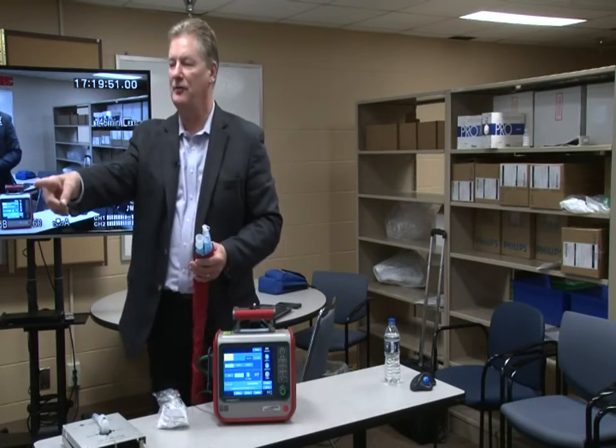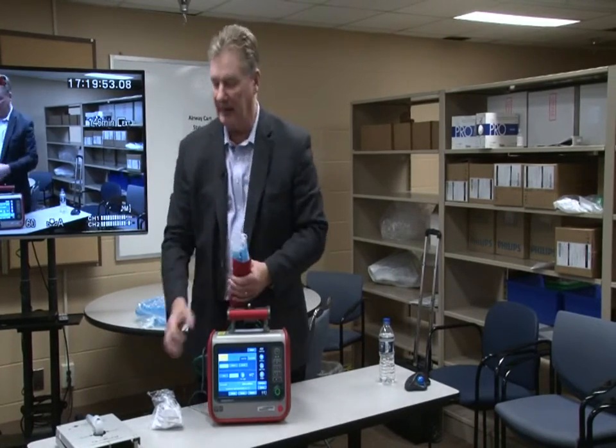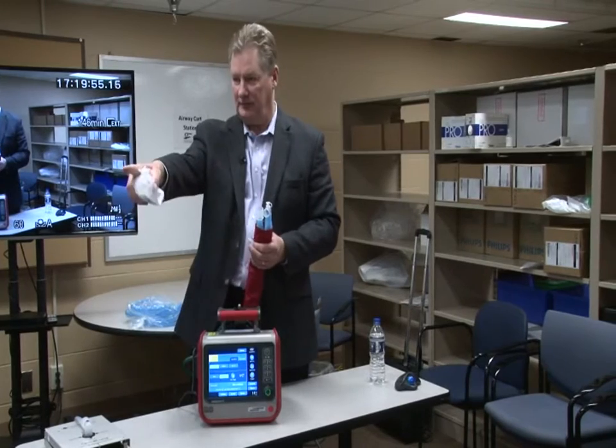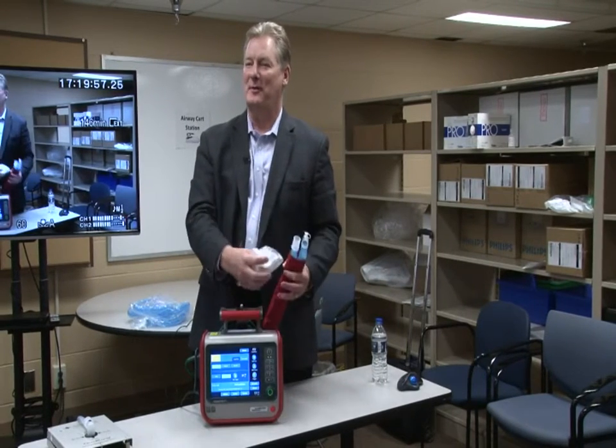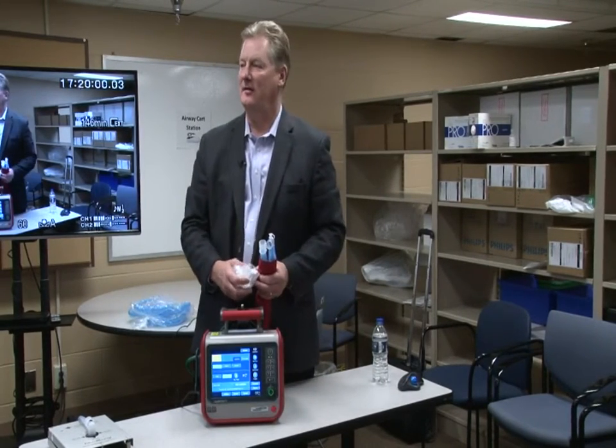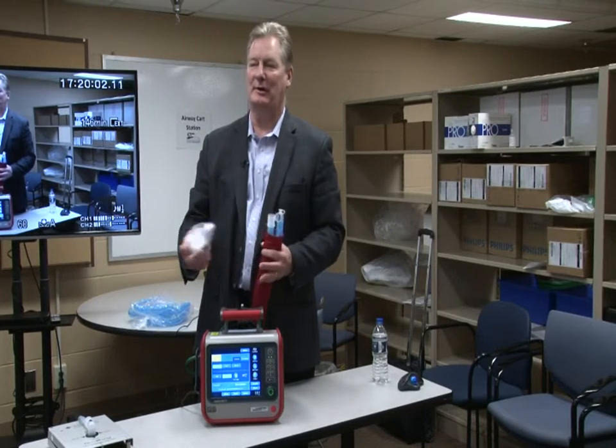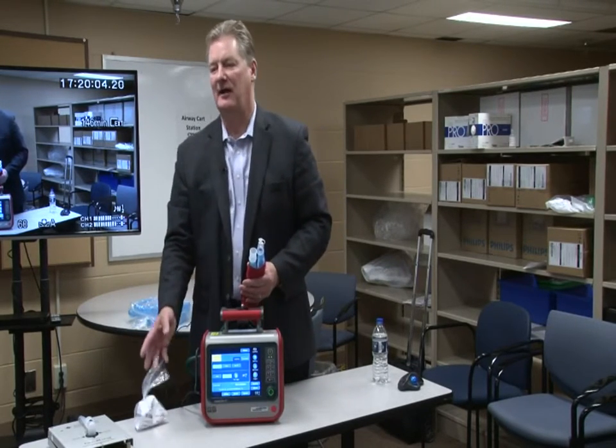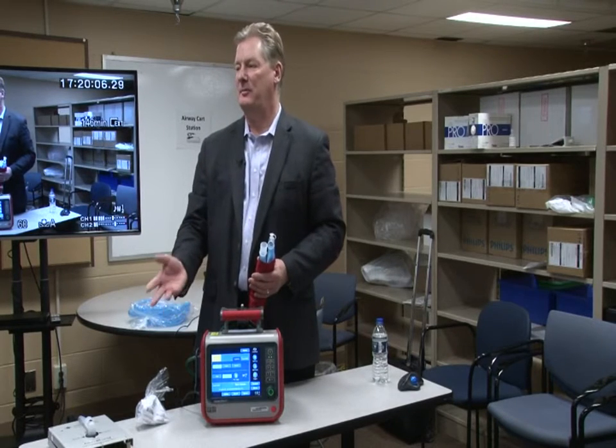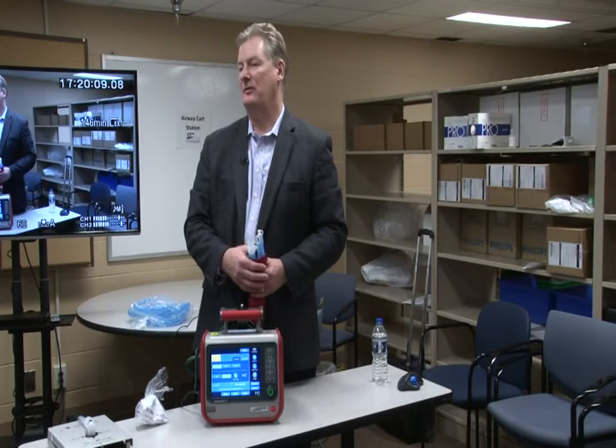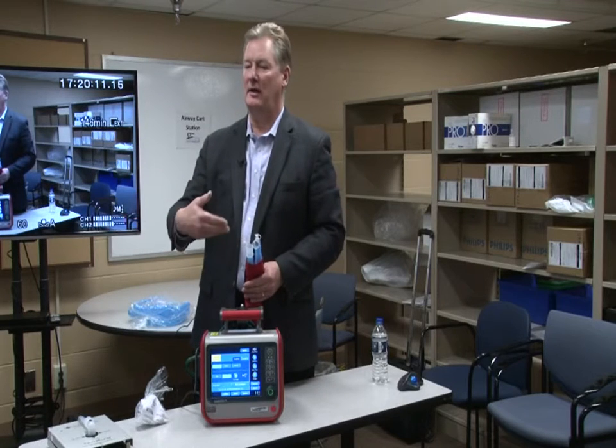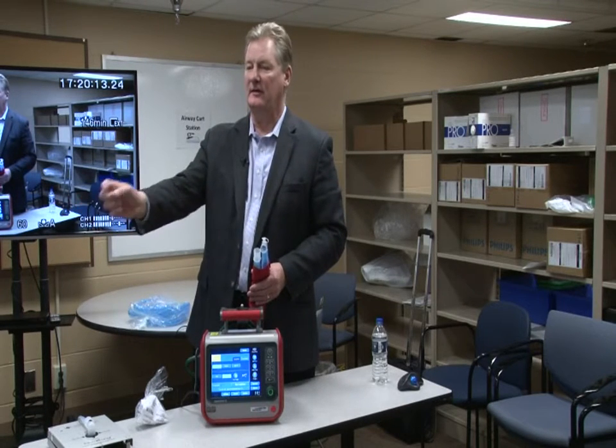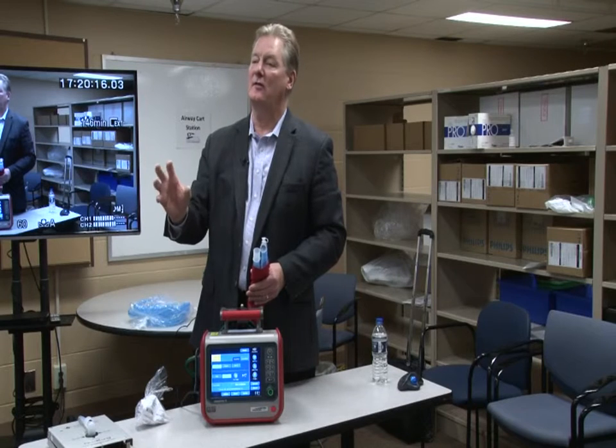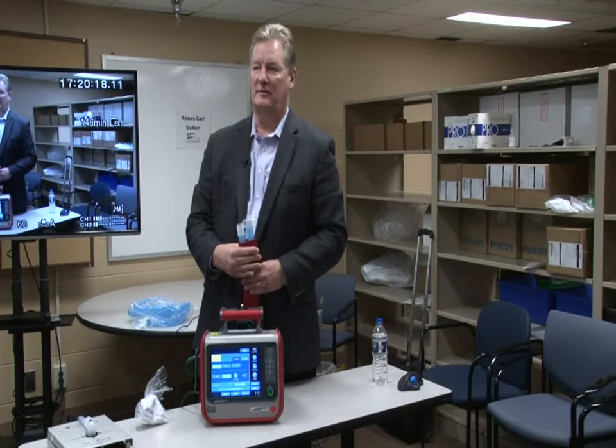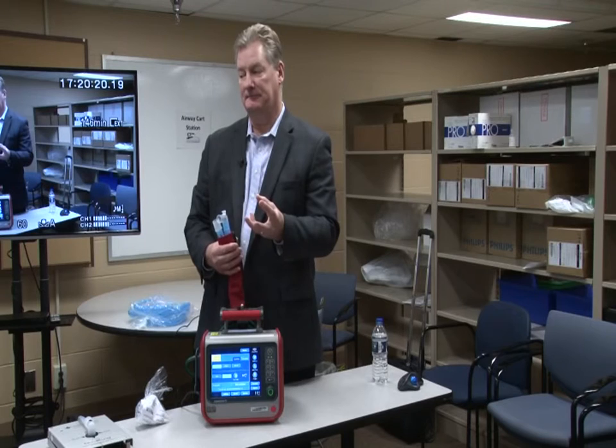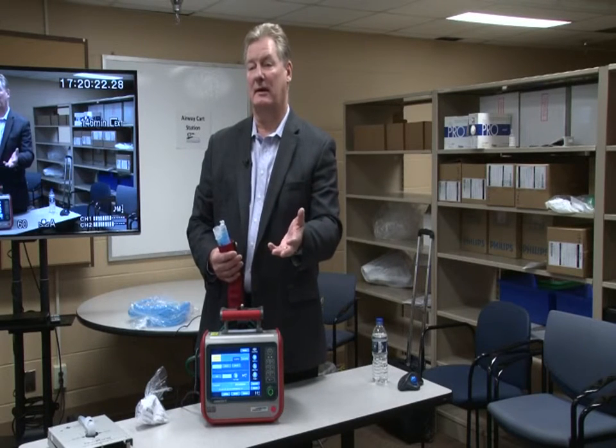But on the circuits that you have there, you'll notice that if I put that on one of those manifolds, you'd have to have two of them, otherwise the other one's not going to connect to the ventilator. So you'd have to have some sort of an adapter. And filtering the gas going from the ventilator to the patient or going back into the ventilator really isn't necessary, because the ventilator is drawing in the room air through the back of the ventilator through that little white dust filter on the back, and then there's actually a HEPA filter inside the ventilator that's changed semi-annually. And so the gas is filtered already going to the patient.